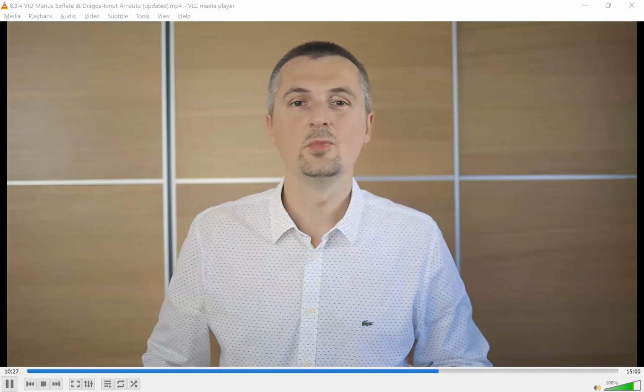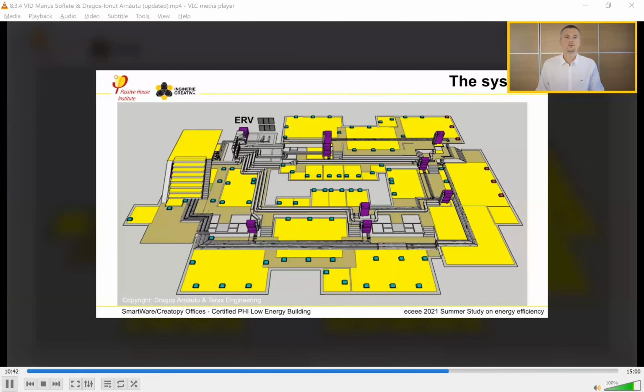The building services such as the heating, ventilation, air conditioning and domestic hot water systems have a significant impact on large buildings and their energy consumption compared to smaller residential buildings built to the Passive House standard. The high internal loads and the fluctuating load profile of an office building highlight the impact of sensible and latent internal heat gains. The ventilation is done by the 8,500 cubic meter per hour energy recovery ventilation unit, which has an effective heat recovery efficiency of 67% and a humidity recovery of 40%.